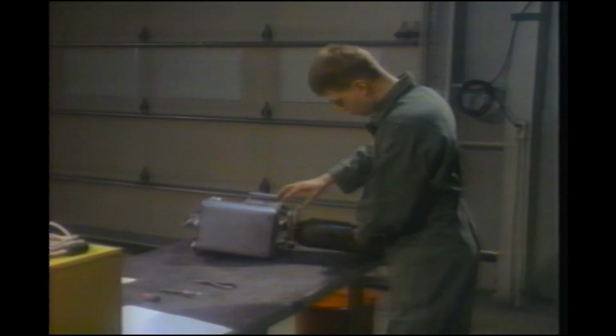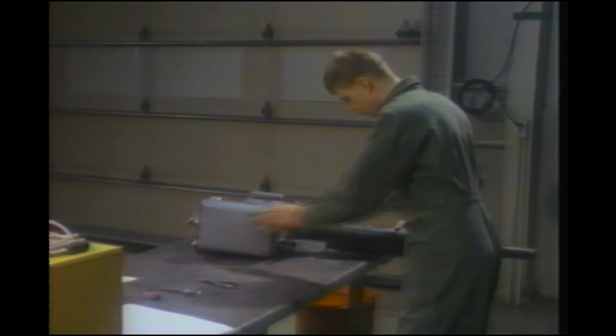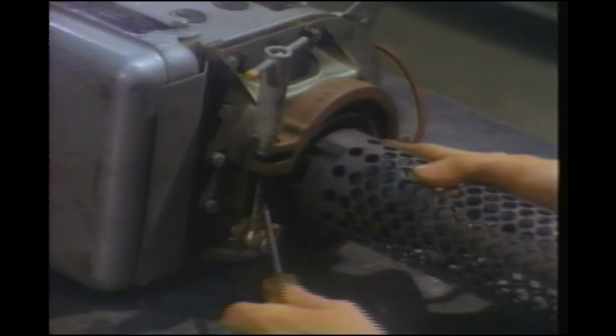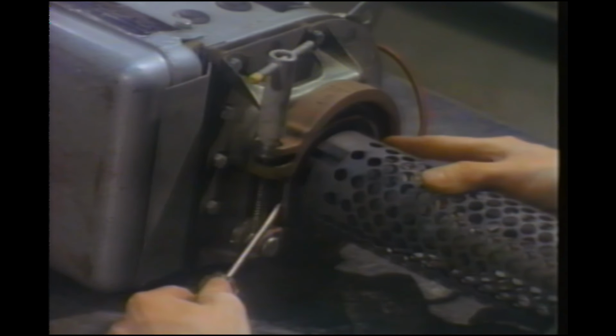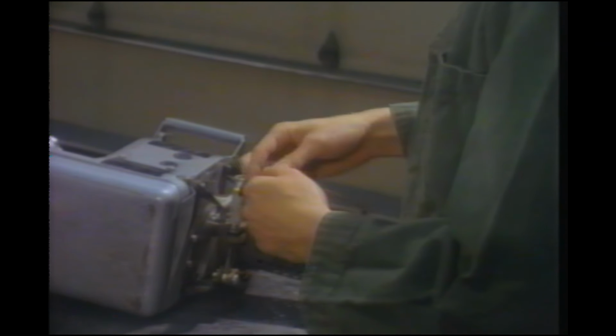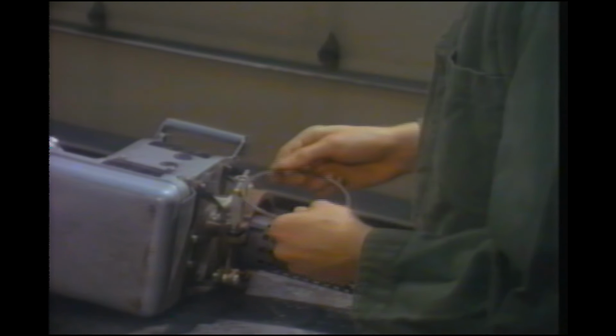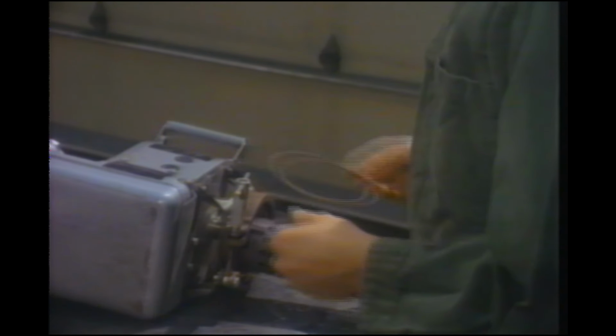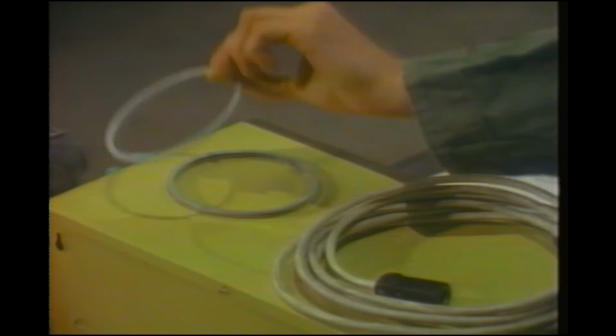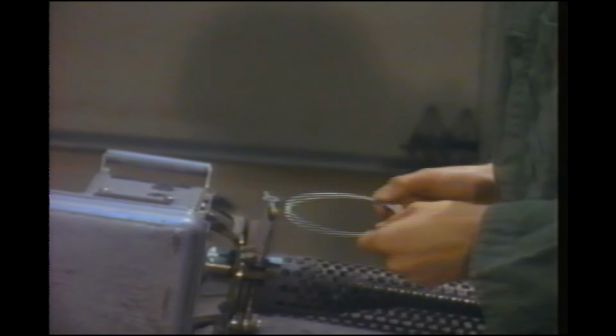Check the wing nut and thread of the quick change coupling as you loosen it. After removing the mixing pipe, remove the gasket. Replace the gasket if it's worn or damaged, as this one was. Inspect the new one before putting it on.